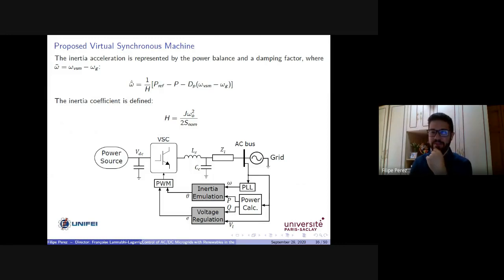If I have an unbalanced system, the first thing is that the synchronous reference frame PLL can become a mess. So I need to improve the synchronization with the grid, considering control strategies that account for unbalanced systems. Also, when I'm doing the DQ0 transformation, I will also consider the zero current, which is not zero when I have an unbalanced system. So I should also include the control law for the zero current, which is the zero term of the DQ transformation from the Park transformation. So I must also include that.